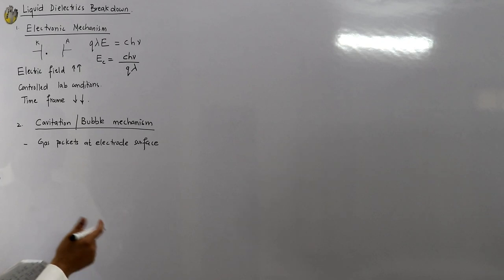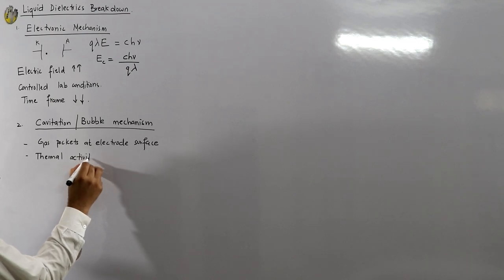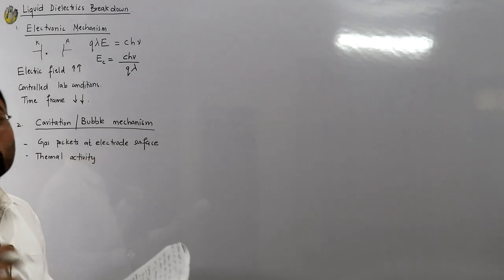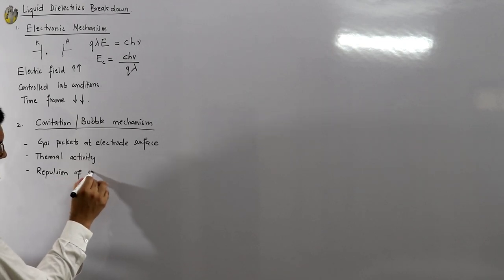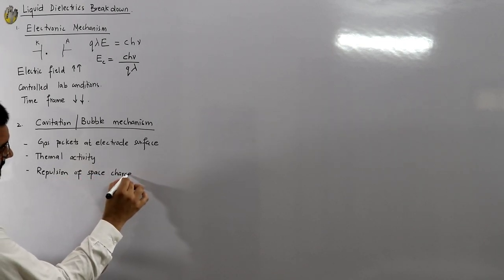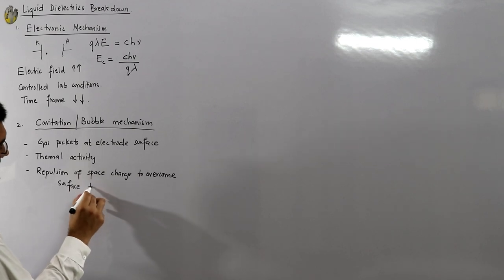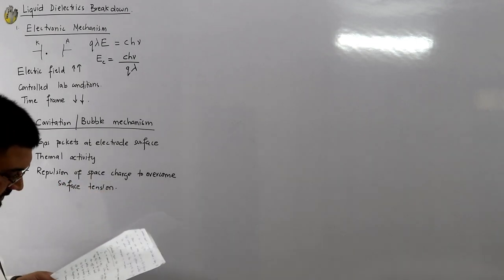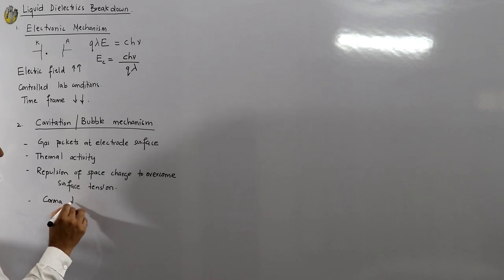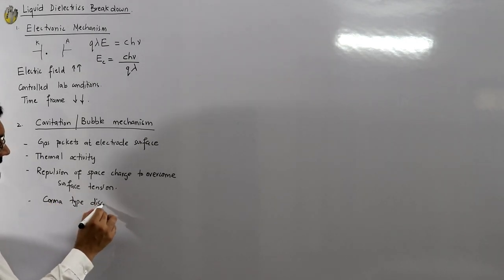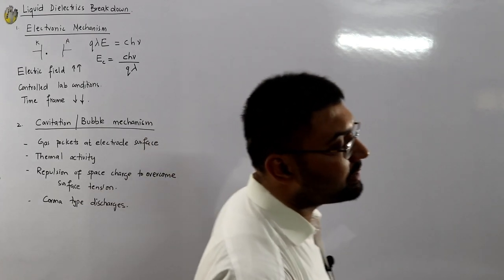Bubbles can form due to some sort of thermal activity, or by repulsion of space charge to overcome surface tension, or due to corona type discharges during operating conditions which produce localized heating. Anyway, formation of the bubble is not the main topic — the key point is that I have a bubble in my liquid dielectric.